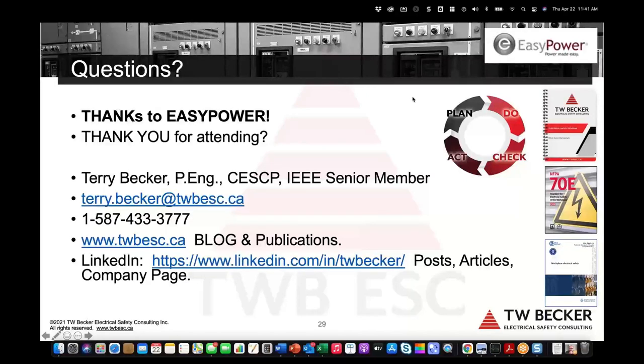So I guess I'm going to have to interpret what you mean by the back. If you have front and back access, and you have a label on that motor control center that says the working distance is 18 inches, it doesn't matter whether you're on the back or the front of the electrical equipment. If you're opening it up and doing one of those discrete work tasks in Table 130.5C for 70E or Table 2 for Z462, it's still, again, a work task.